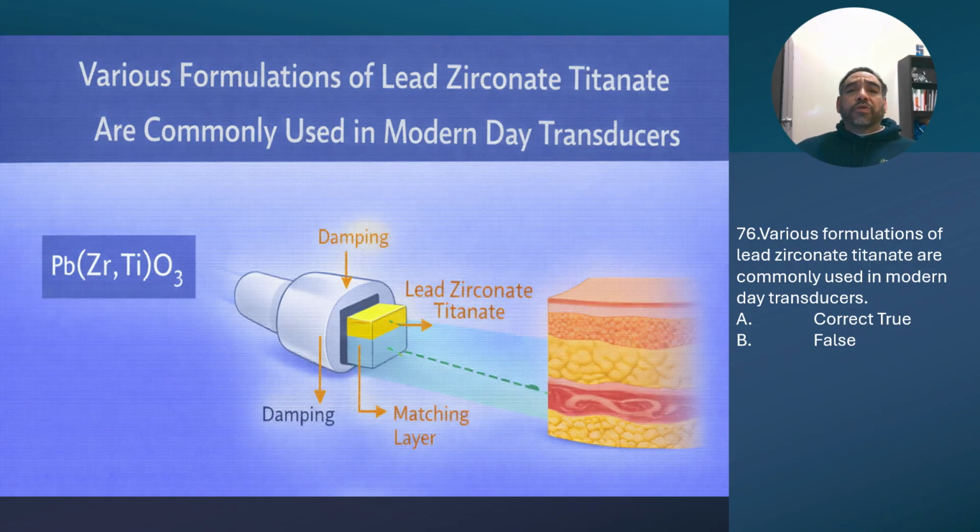Awesome people who create all of our stuff, our PZTs, our resistors, our semiconductor materials engineers, where would we be without them? Anyway, back to the question. So we have different clinical applications like cardiac, vascular, abdominal, high frequency probes, right? And so they require slightly different performance characteristics, and that's achieved by tweaking that PZT formula. Again, something you don't have to do, just know that it's done. There are materials engineers, and this is what they live for. They cook.